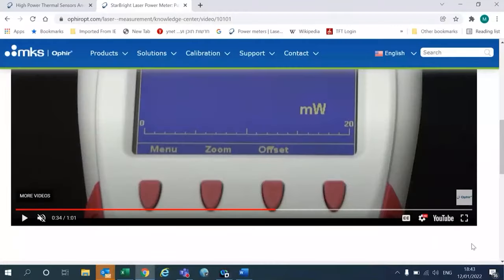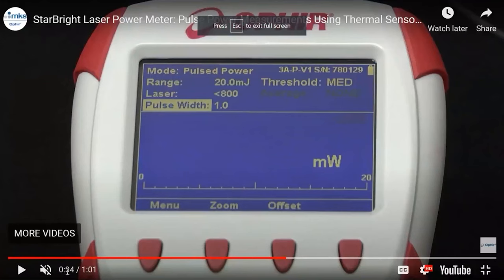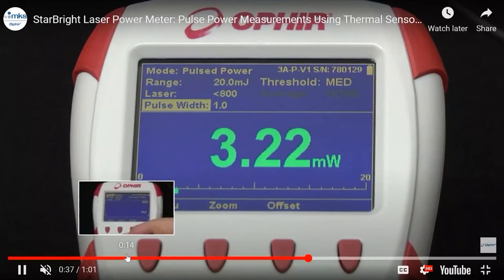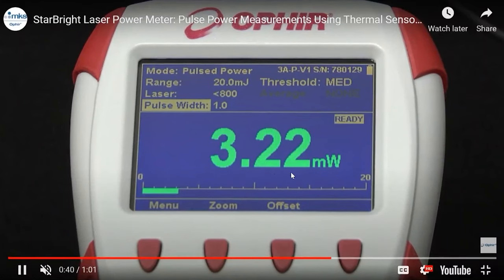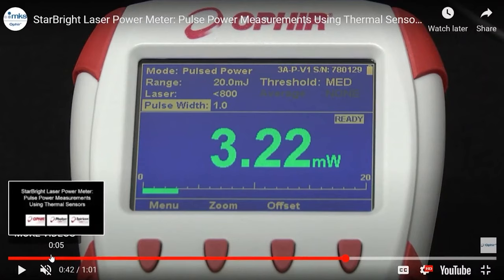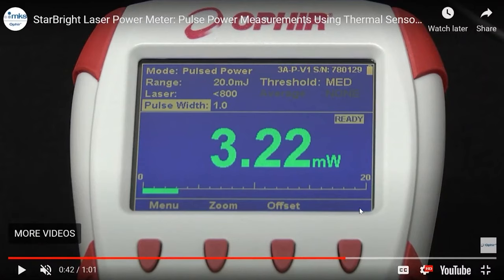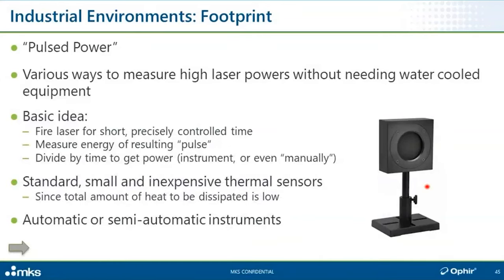This is just what it looks like on an Ophir instrument with a sensor. Okay, and this is what it looks like. Notice it prompts the user to enter the pulse width. We're in pulsed power mode. And when the laser fires, we get the power. You'll notice this is only like 3 milliwatts. I did this in my office for the purpose of demonstrating it, so I couldn't quite do the 10 kilowatt thing, but you get the idea. So for this purpose, at Ophir, we've given a lot of our moderate power sensors a very high energy scale so that we can measure these multi-kilowatt beams using this trick.